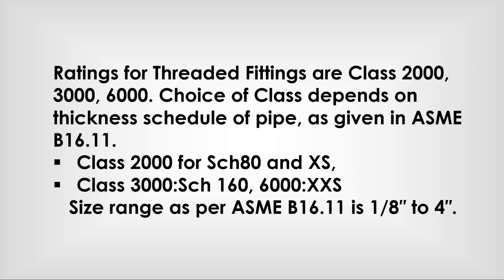Choice of class depends on the thickness schedule of pipe, as given in ASME B 16.11: Class 2000 for Schedule 80 and extra strong; Class 3000 for Schedule 160; Class 6000 for double extra strong. Size range as per ASME B 16.11 is 1/8 inch to 4-inch.